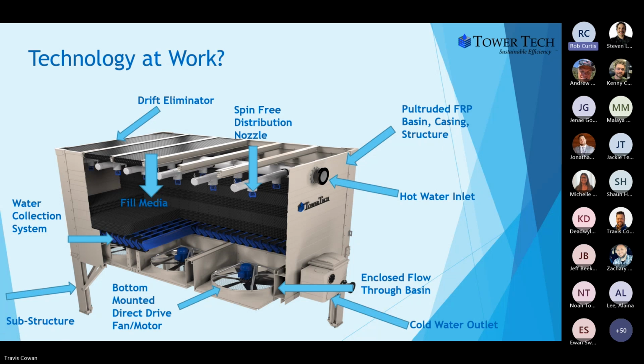And so with that, if we have on a single module a fan go down or a motor go down, you can still keep your other equipment operating while you're replacing that mechanical motor or fan. So we have redundancy, we have reliability built in with that. Last up on that is that mechanical equipment operates in the intake airstream. So the coolest air is coming in and contacting that fan and motor, the coolest, driest air. As it goes through the cooling tower, it gains heat and moisture. And that is typically where traditional mechanical equipment is located. So we put it in a less compromised environment from a longevity standpoint.